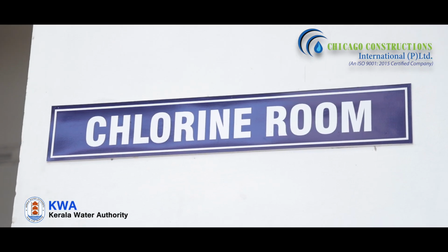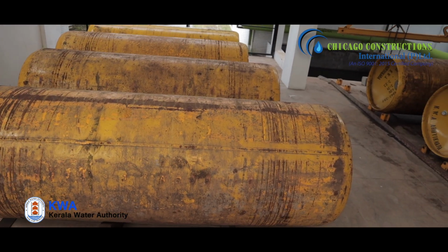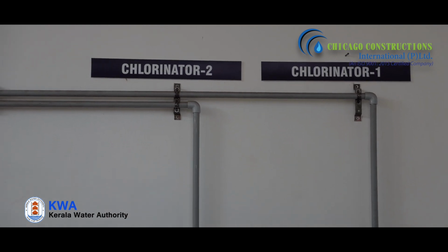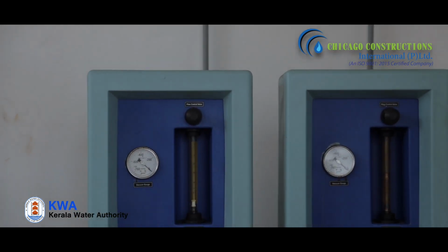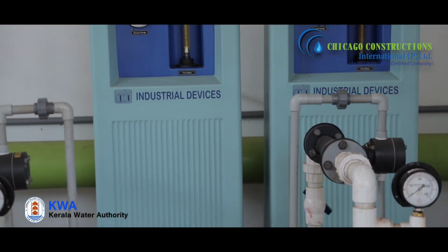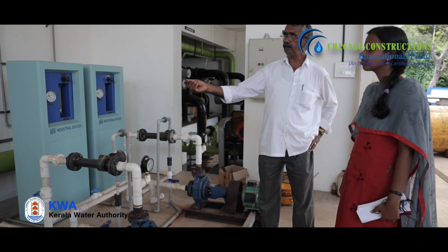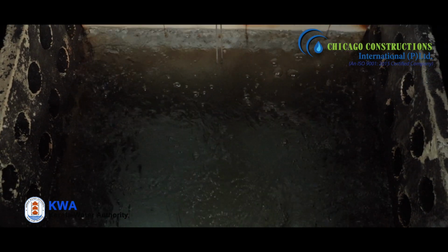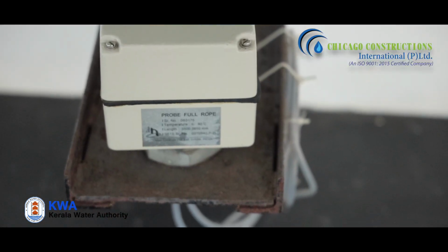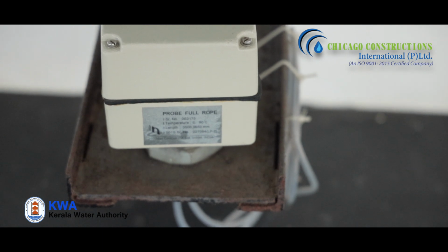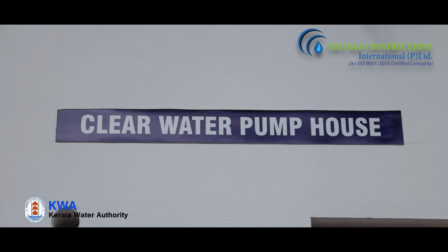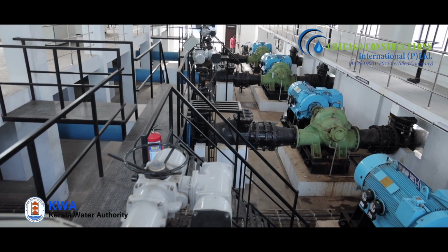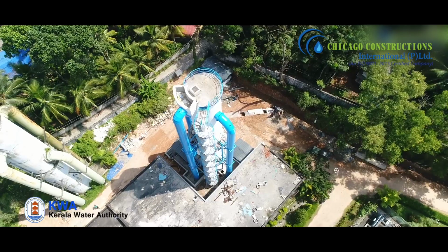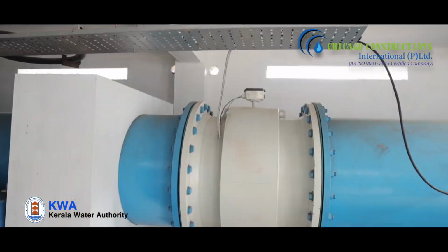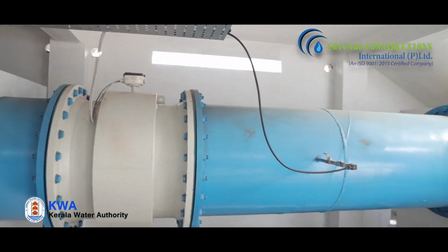For chlorination of filtered water, 1000 kg chlorine gas cylinders are attached to 2 chlorinators with 15 kg per hour vacuum feed capacity. Necessary safety precautions have been provided at the WTP. As part of that, a neutralization pit is set up near the chlorine room. The chlorinated fresh water is then stored in 2 clear water sumps, each measuring 17.2 x 32.28 x 3.5 meters. From there, 4 horizontal centrifugal pumps of 350 kW are used to pump the treated water to the break pressure tank through a 1000 mm MS spirally welded pipe of length 587 meters.